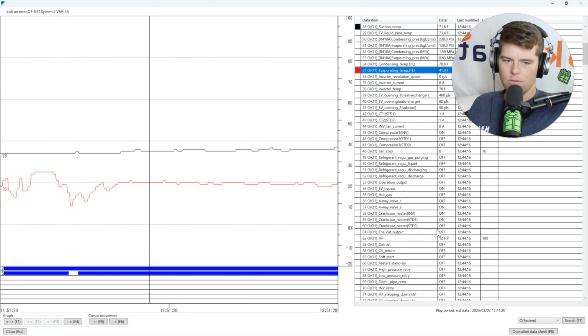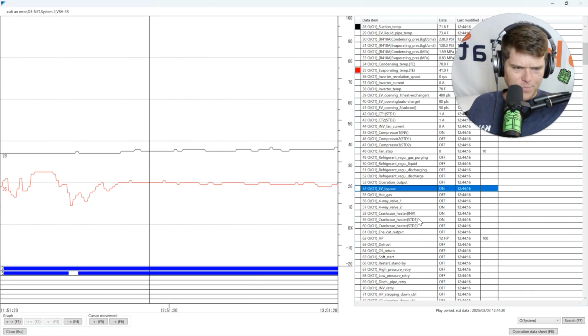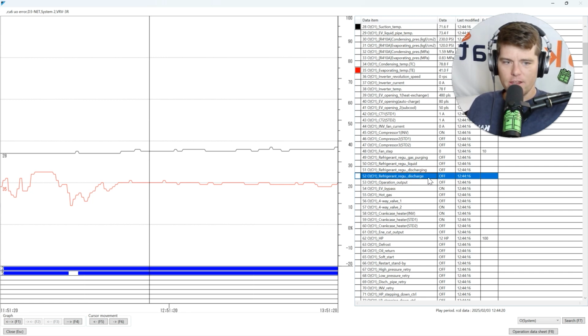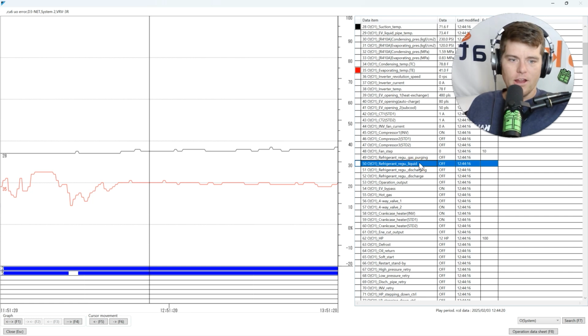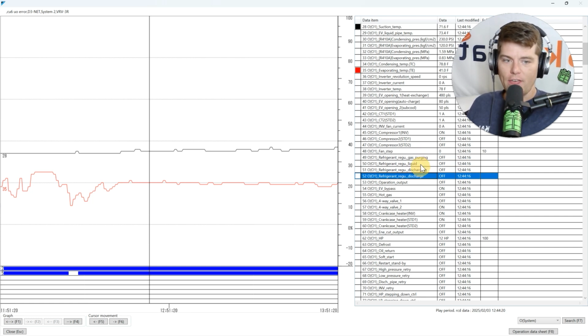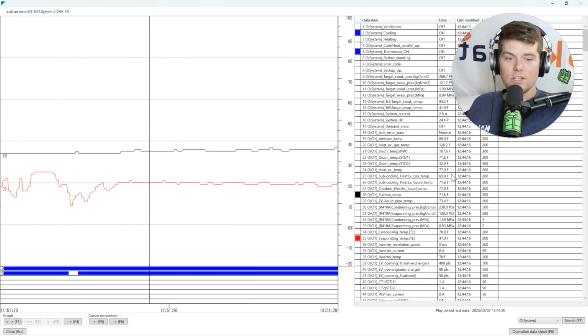Let me just show you. Ooh, I'd love to show you. You've got your EV bypass here. You've got other, let's see here, refrigerant regulator discharge, refrigerant regulator discharge, refrigerant regulator liquid, refrigerant gas purge. These are all your solenoids on that circuit for that system.